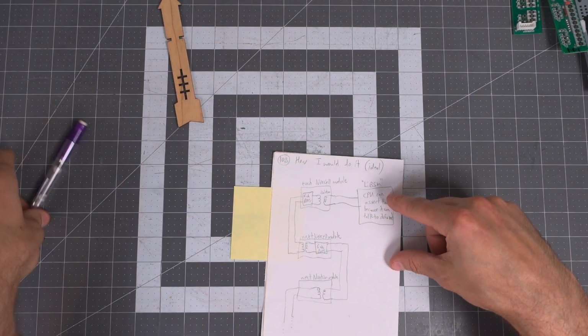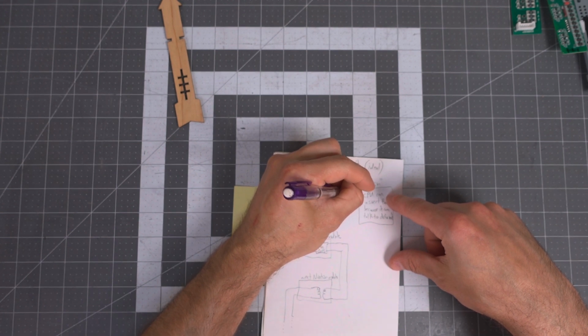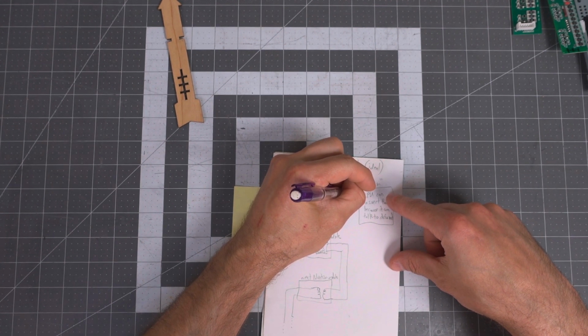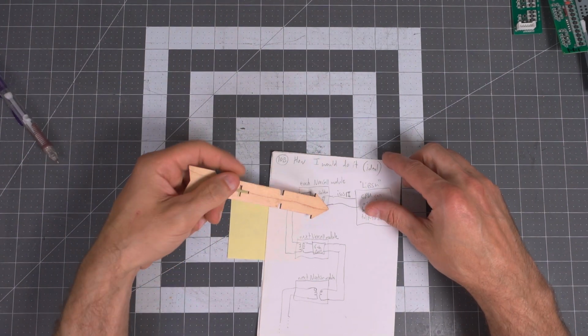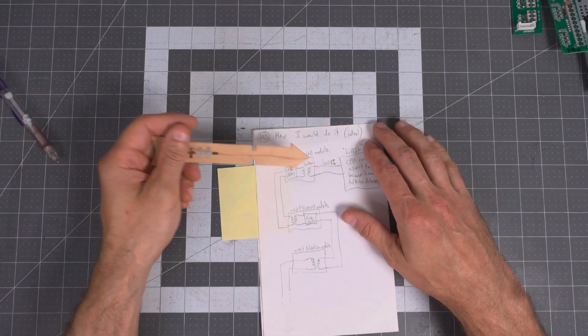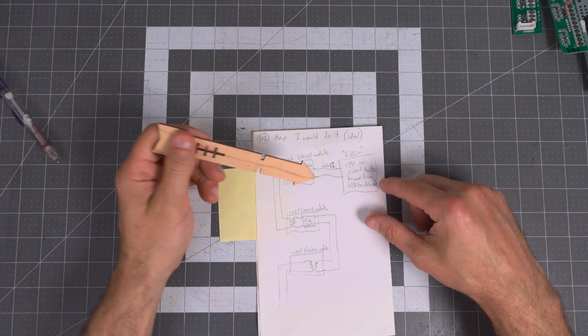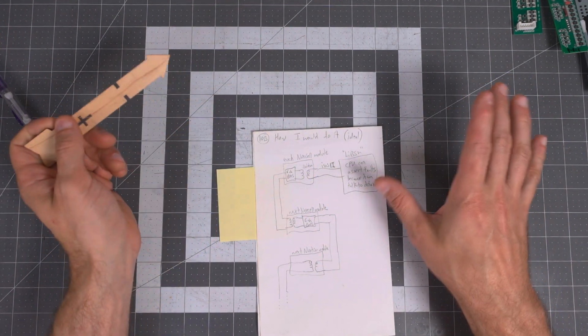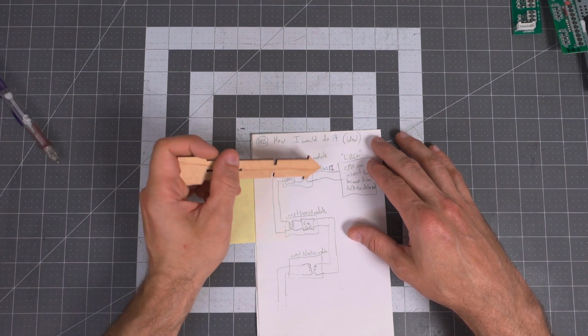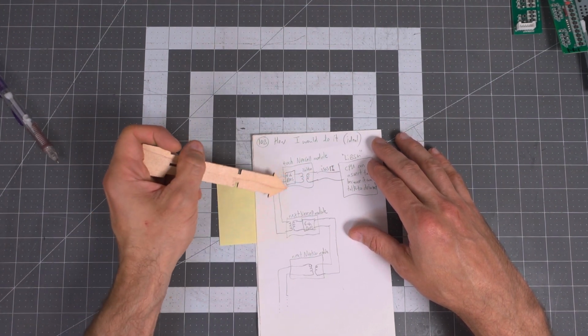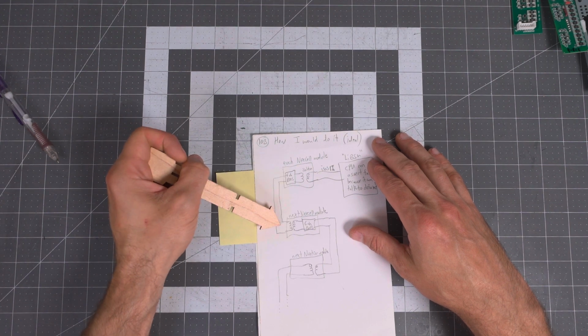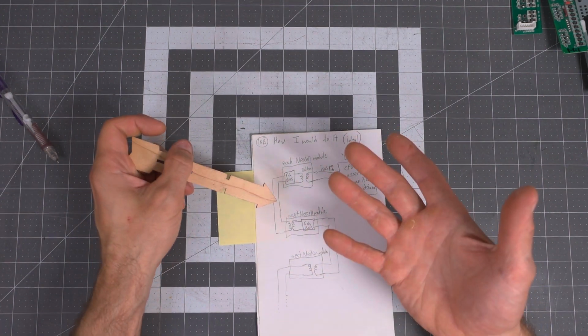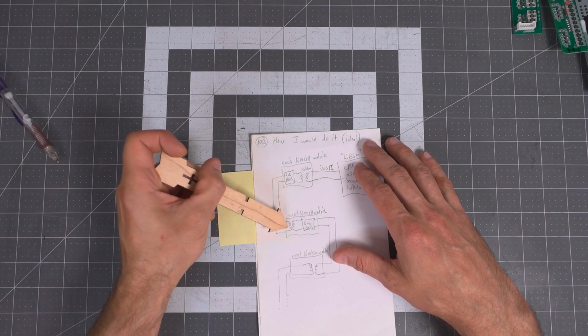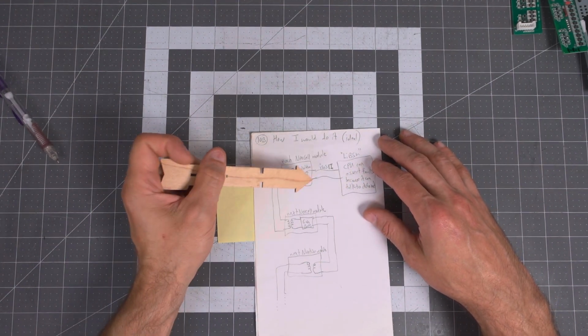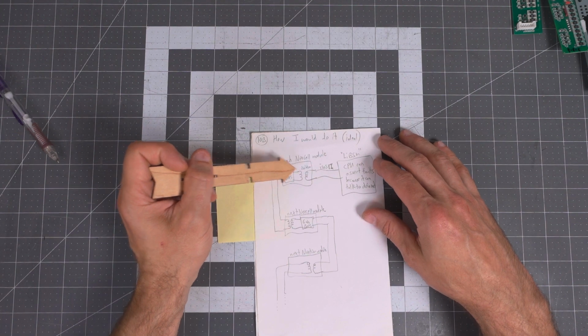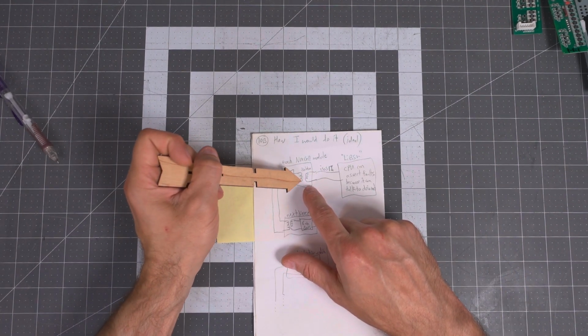It has what's called an ISO SPI bus. Just look it up, it is a fully galvanically isolated electrical communication interface. It's specifically designed for battery management, or at least originally was, it's used for lots of things now. This is a 2-wire, no external power required, you literally have a pulse transformer, an isolation transformer, inside. You'd ideally want it on both sides so that the external user signals aren't energized to the pack voltage. So you'd have the same isolation transformer on both sides of every cell, and you literally have an ISO SPI. So there's this ISO SPI channel, and the LTC parts, at least, have a cascading ISO SPI.